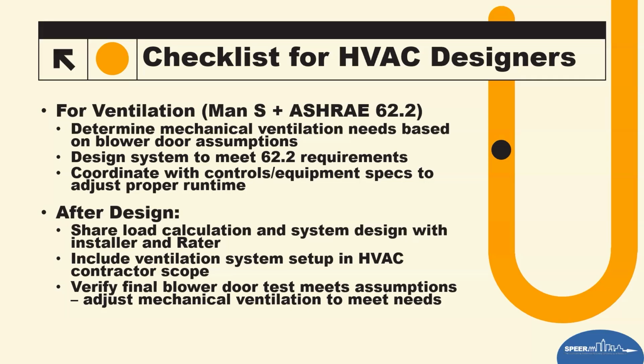So I hope all of that wasn't too confusing. I tried to keep on track and not get lost in the weeds with a lot of things. I hope a lot of that made sense. What I really was trying to do was just to connect the dots as to why blower doors are important. But there's another dot at the end, which means verifying that the blower door met the assumptions of the Manual J and S for sizing of the equipment. And if that's done, then you can rest assured, most likely, that within 10%, 15% max, you've probably got the correct size for that equipment.